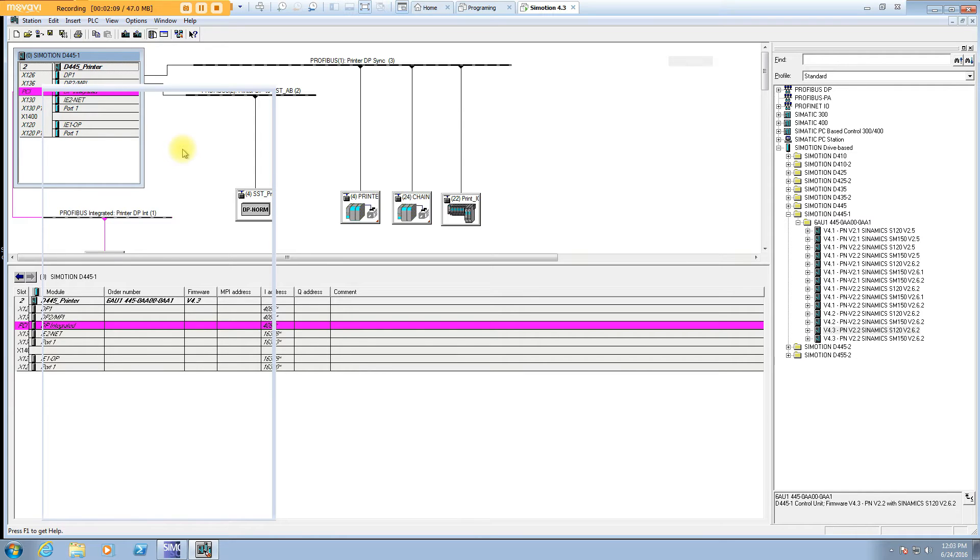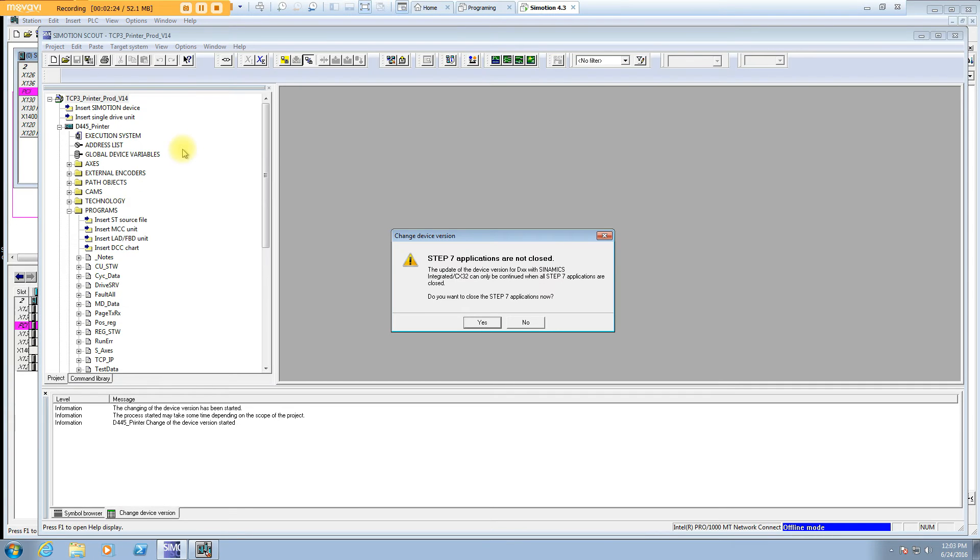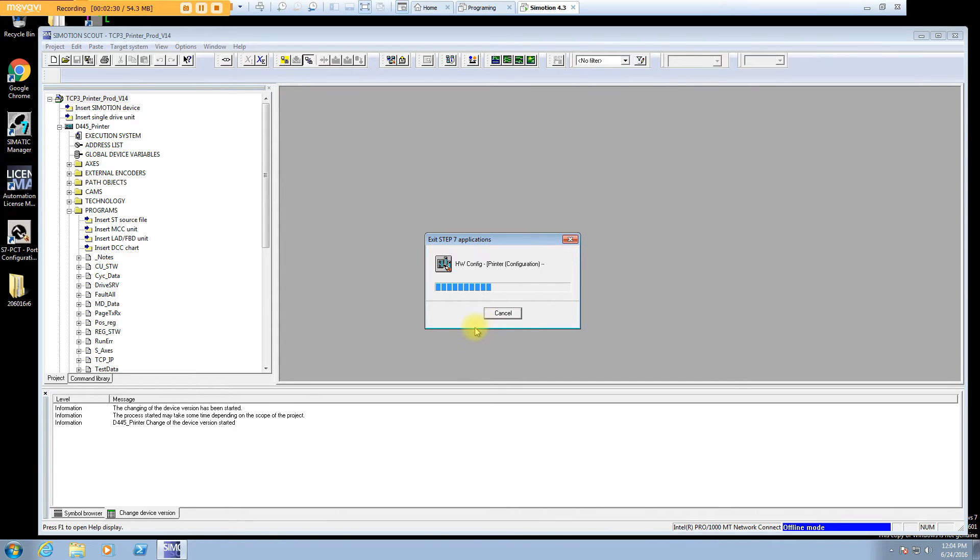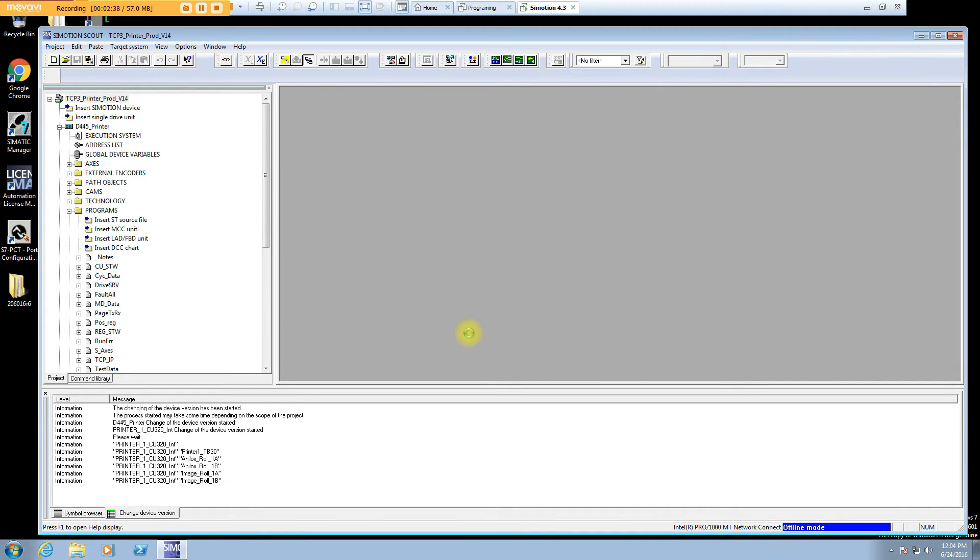If you're changing a lot of things, going to the next generation processor, like the dash 2 processor, this is a dash 0, you'll get errors because there's new networking information. But you've got to be careful, you can't just do that without upgrading the power modules. So we're going to stick with just going from an old dash 0 processor to a dash 1 processor, so we can reuse our existing power modules because there's a lot of them.